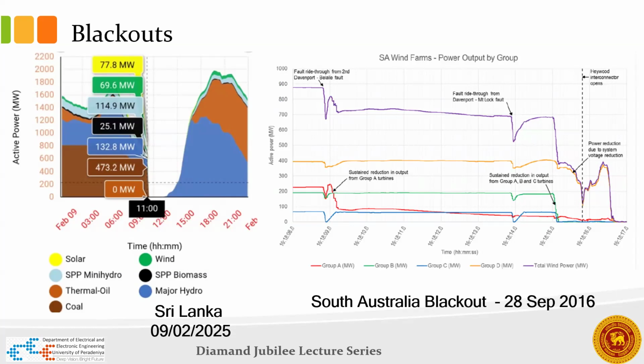There are 4 types of wind turbines shown in yellow, red, green and blue. These wind turbines were supposed to ride through the fault during the disturbance, and you can see that some rode through but some couldn't. Then there was a second lightning strike, and again you can see a few managed to ride through the fault without any issue.